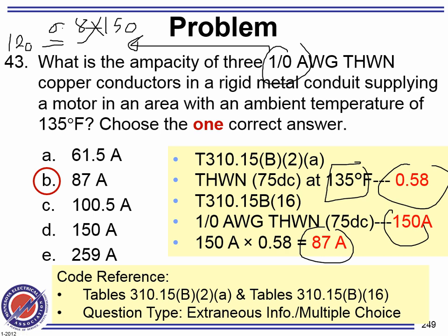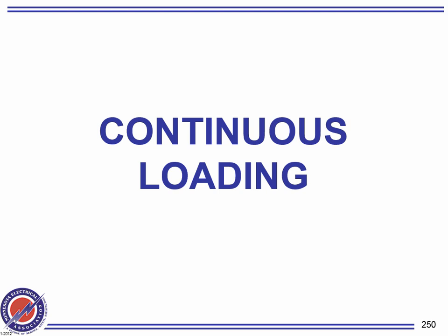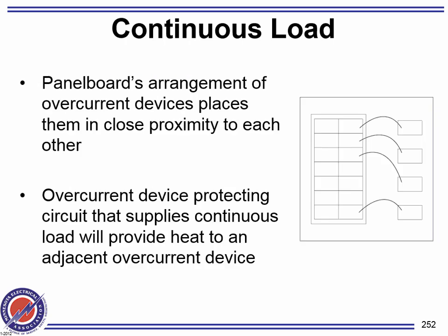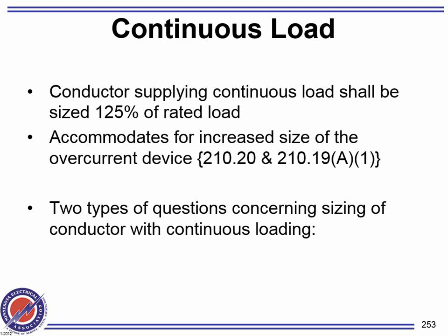So yes, you have to look at the continuous load. Find the amps, cut it by 80%, that's all. You read and compare them. But in this case, that wouldn't change our answer. Speaking of the devil, continuous load. For continuous load, guys, we size the breaker as well as the conductor based on 1.25.